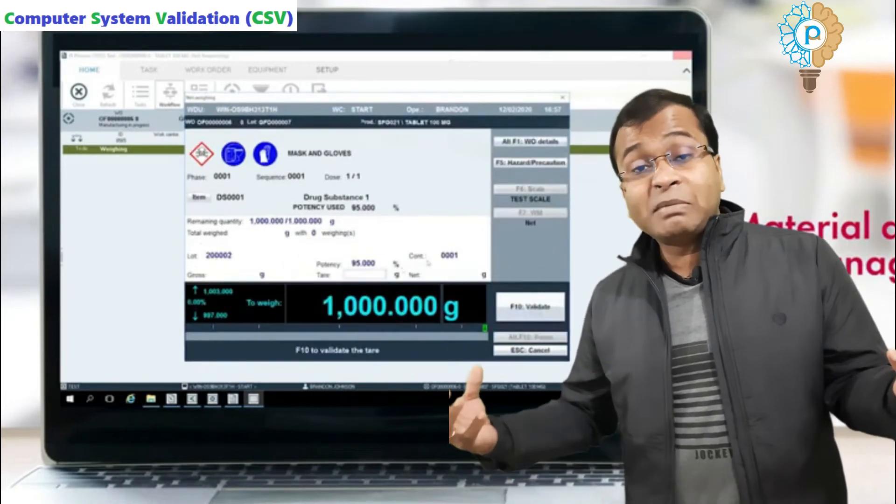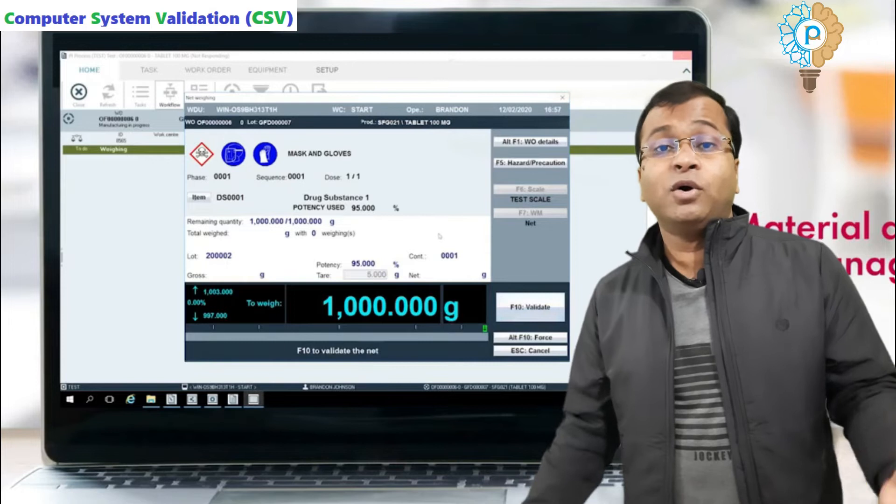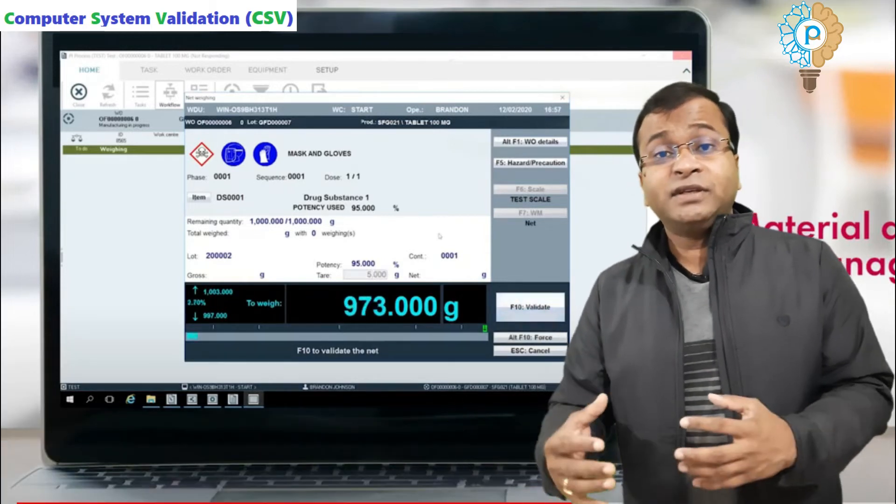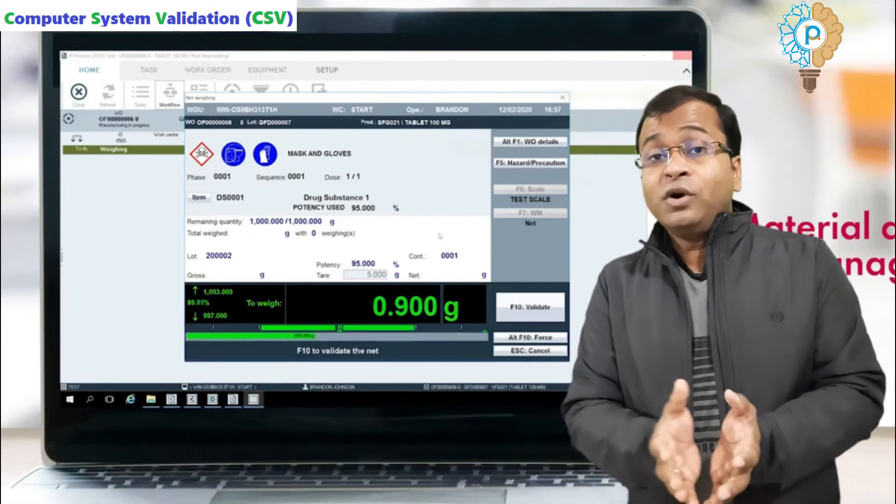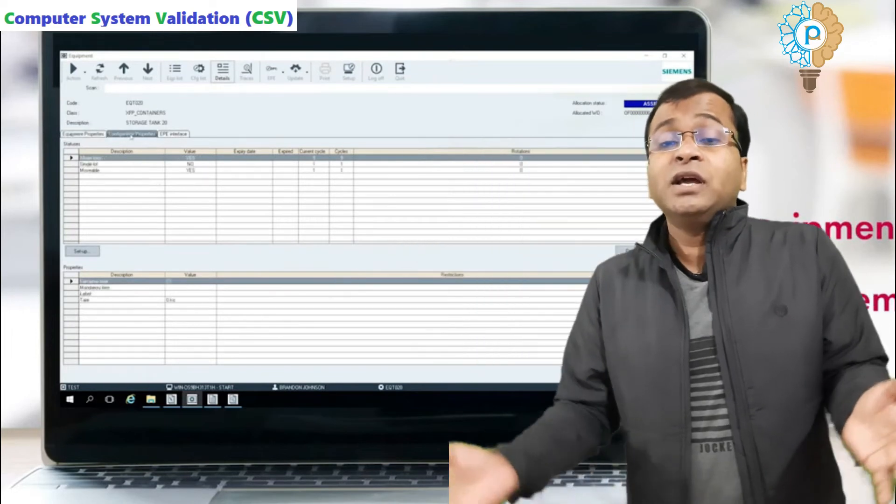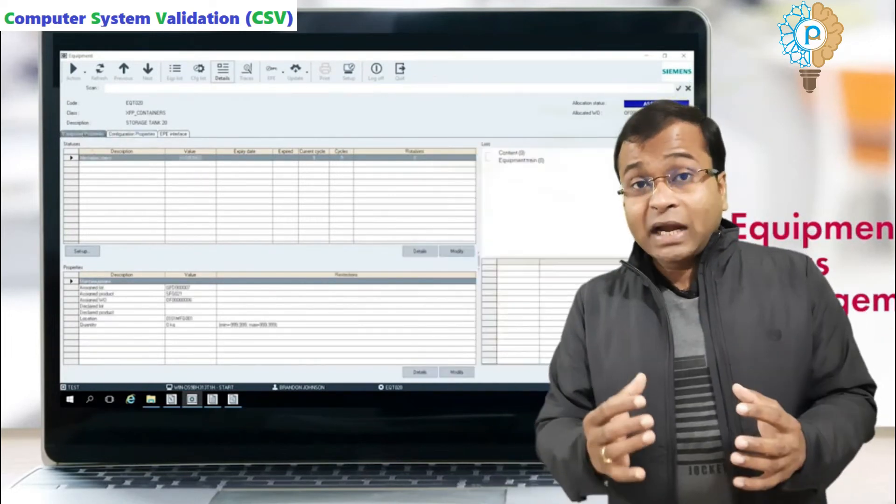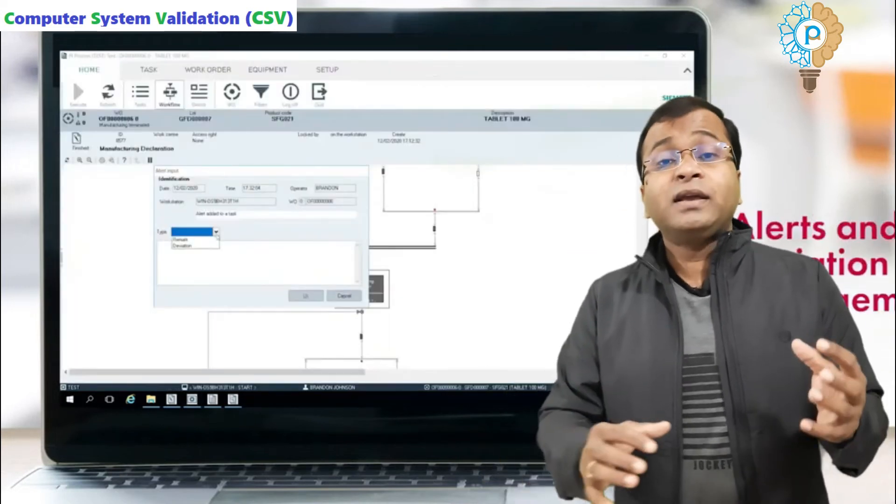Category 5 software is created as per the pharmaceutical manufacturing company only, because the process is different. Different types of companies have different manufacturing processes, and different product manufacturing processes are different, so the software has to be created as per the manufacturing process only. During Category 5 software creation, you have to remember a lot of things like: software qualification needed or not, password control, storage, backup, auditor review, and you should prepare one risk assessment.